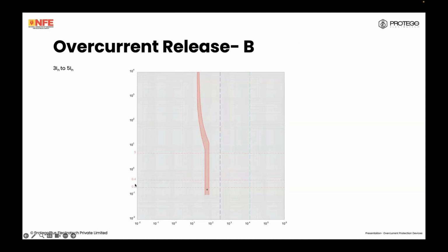I've just highlighted 0.2, 0.4, and 5 seconds because those are the common times required for TN systems, 0.4 and 5 actually. It will trip for between 3 to 5 times IN. For a C curve MCB, this is between 5 to 10 times IN. For a D curve MCB, this is between 10 to 20 times IN. For a K curve MCB, I put a star here because these are manufacturer defined.